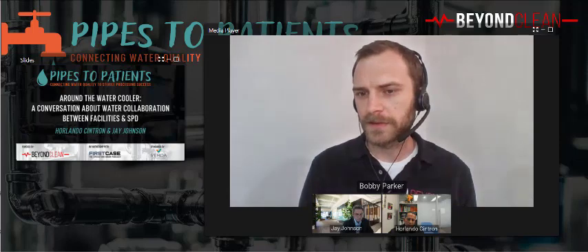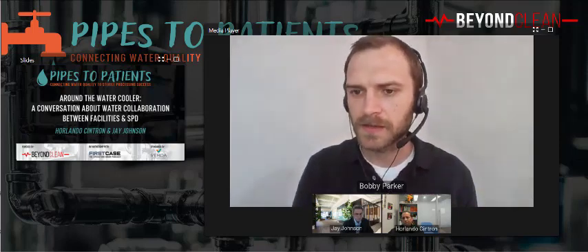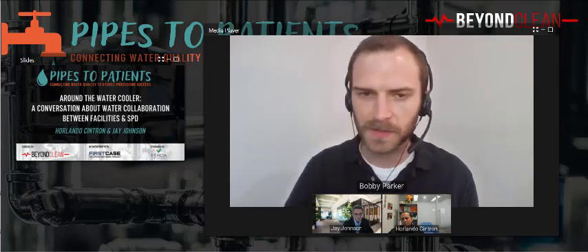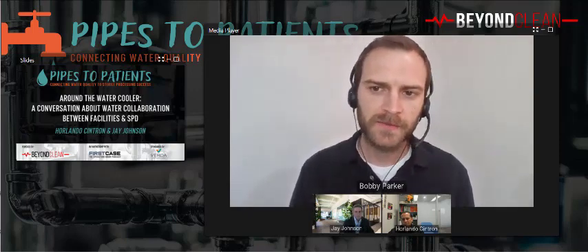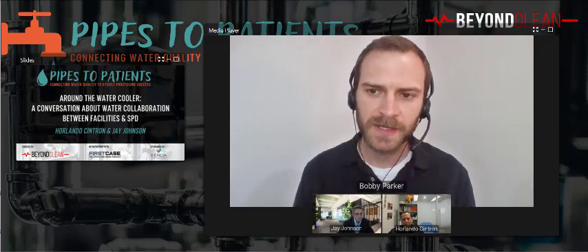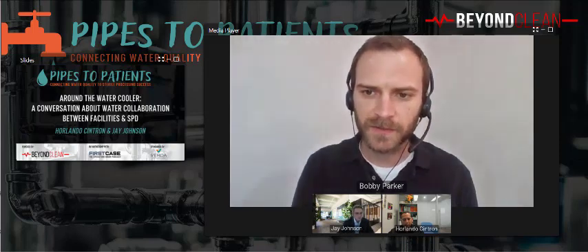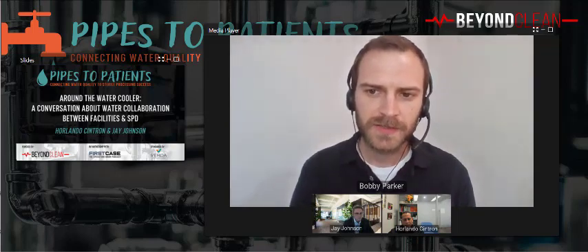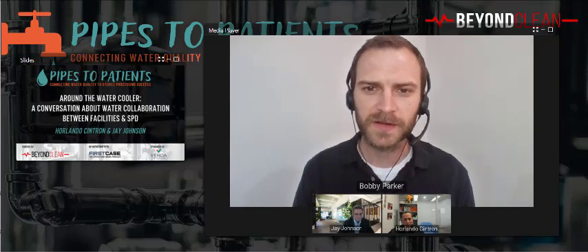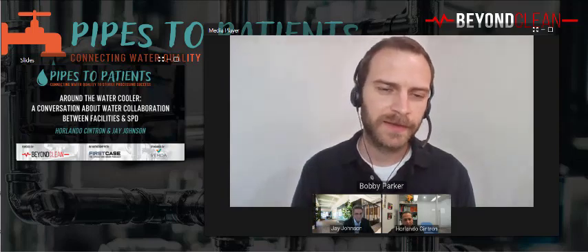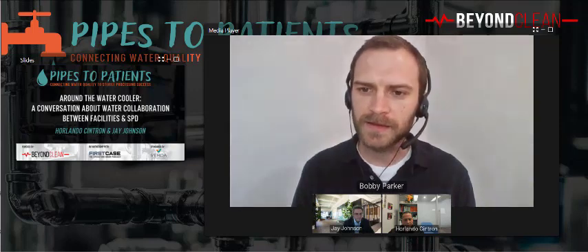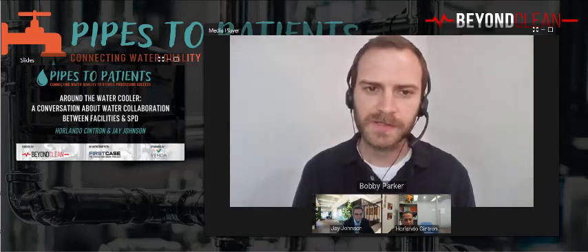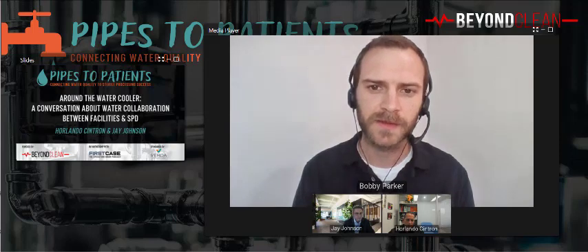One of our listeners threw in a question along these lines about collaborating over equipment issues. They've noticed staining on some surgical instruments, and have a recommendation from the manufacturer that the reverse osmosis system should be changed out every 4 to 5 years, but it's been 11 years since the equipment was serviced. So there's some finger pointing going back and forth between facilities and sterile processing about what ought to be done with that equipment, and whether it's working appropriately. Any advice on that specific reverse osmosis filter situation, or in general about collaborating around that type of issue?